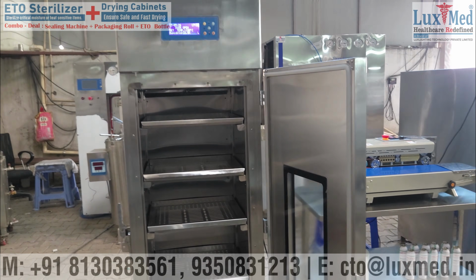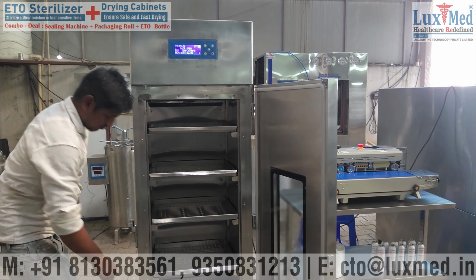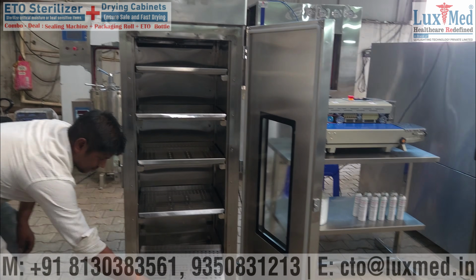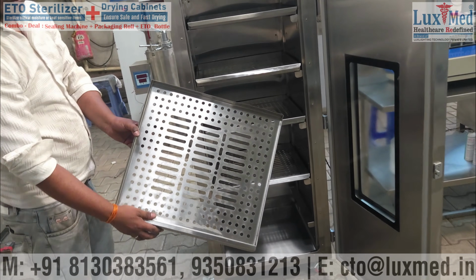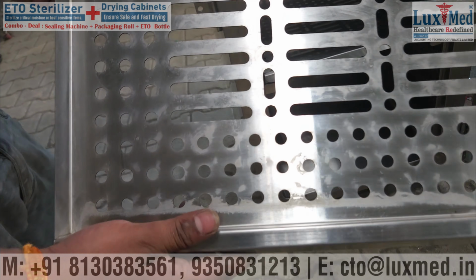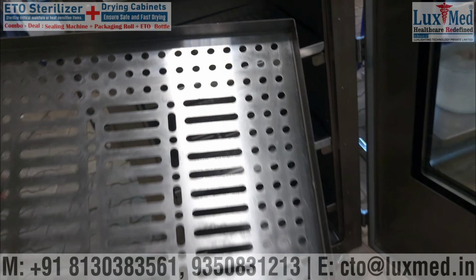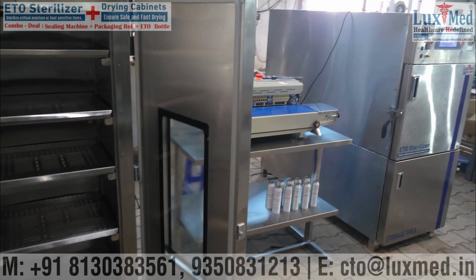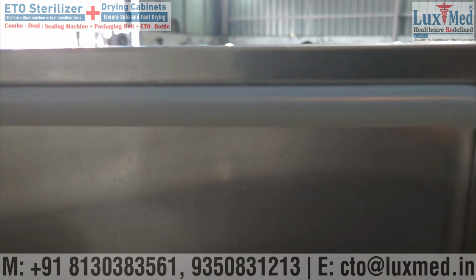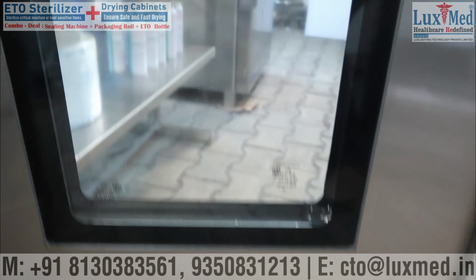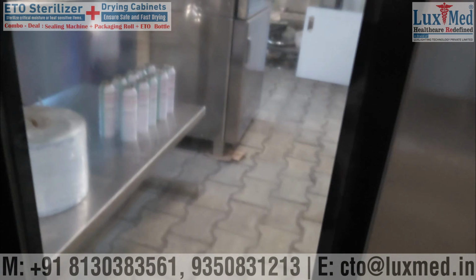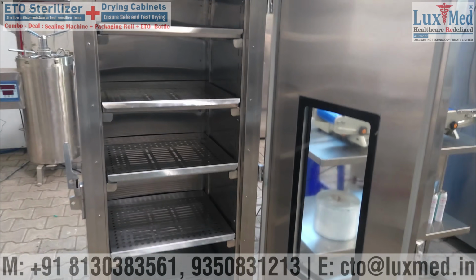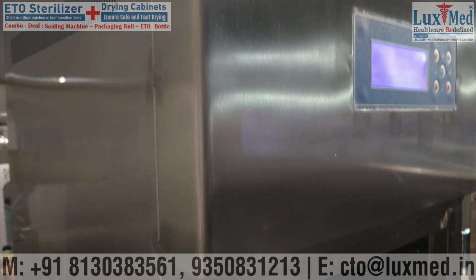1. LuxMed ETO sterilizer. What it is: a specialized chamber that uses ethylene oxide, C2H4O, gas to eliminate bacteria, viruses, fungi, and stubborn spores. It achieves this at relatively low temperatures, usually 37 degrees Celsius to 63 degrees Celsius. Applications: ideal for heat-sensitive and moisture-sensitive items that would be destroyed by traditional steam autoclaves. Common loads include catheters, plastic tubing, rubber products, surgical instruments, and delicate electronics.